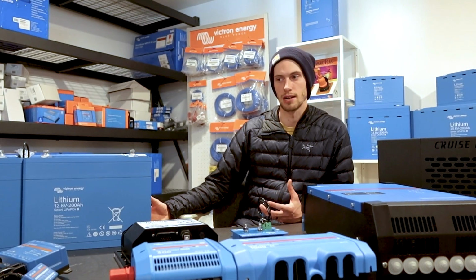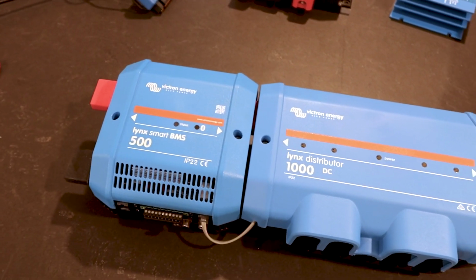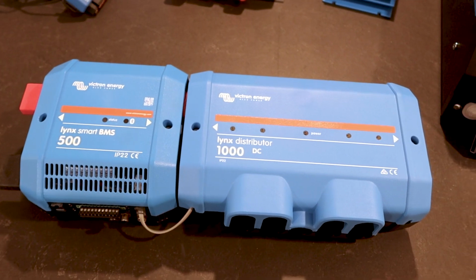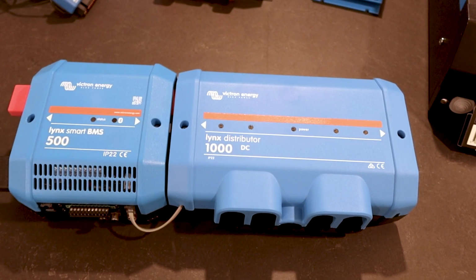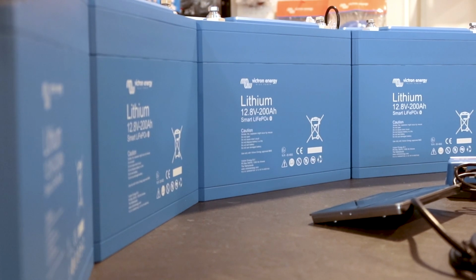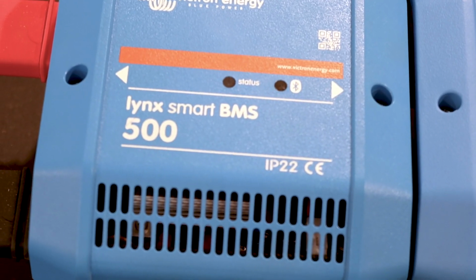The BMS is designed to protect the batteries from under or over voltage and under or over temperature. If you need to shut down the loads, you don't want to open the contact and cut off the whole battery from being able to charge. So these batteries can communicate with the BMS to just turn off loads while still allowing charge.